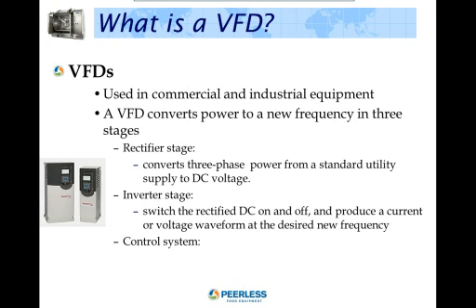VFDs and how they work. For more than 40 years, variable frequency drives, or VFDs, have been a critical component of commercial and industrial systems. Today, their fundamental usage has remained the same, while technology has evolved and improved, yielding drives that are better able to reduce energy consumption and improve reliability while extending equipment life. A VFD is an electronic controller that adjusts the speed of an electric motor by regulating the power being delivered. VFDs provide continuous control, matching motor speed to the specific demands of the work being performed. They are an excellent choice for adjustable speed drive users because they allow operators to fine-tune the process while reducing costs for energy and equipment maintenance. In other words, they help you use the energy you need and no more.